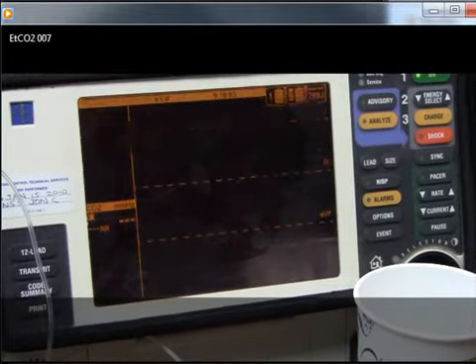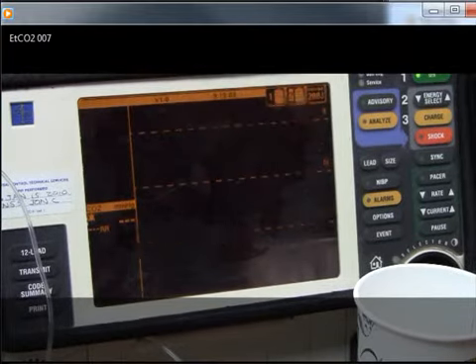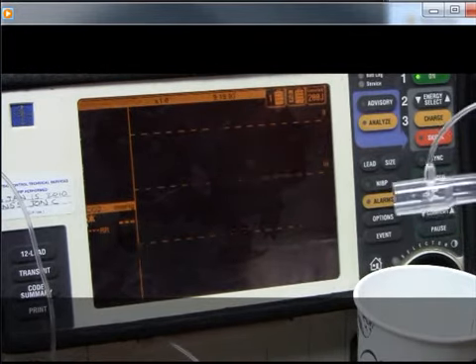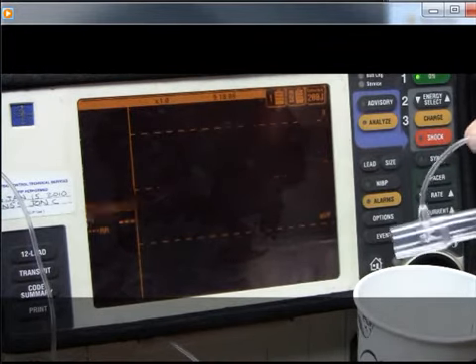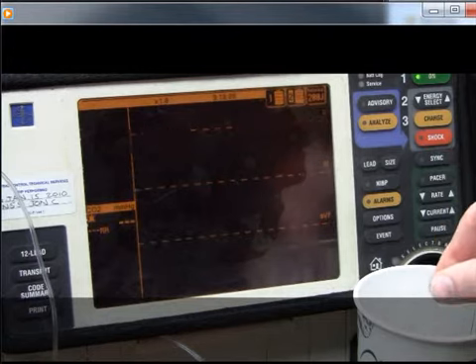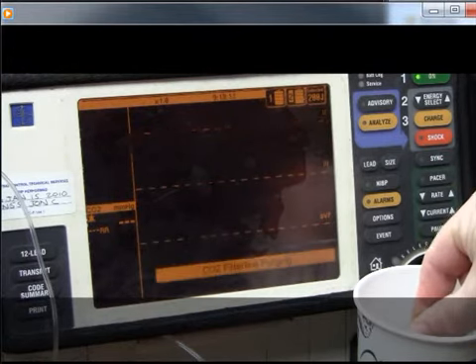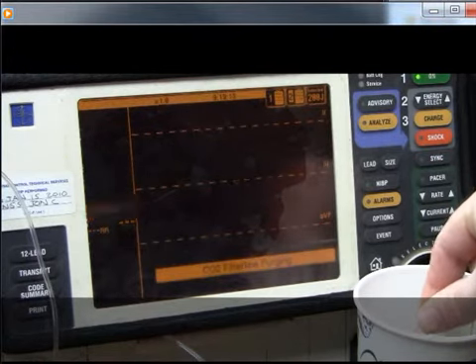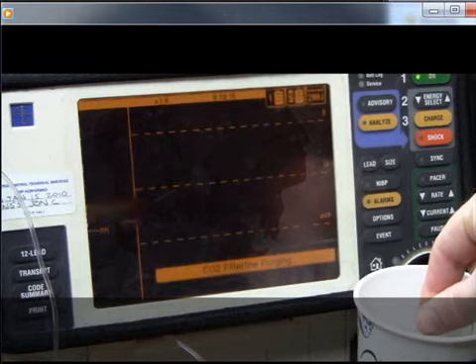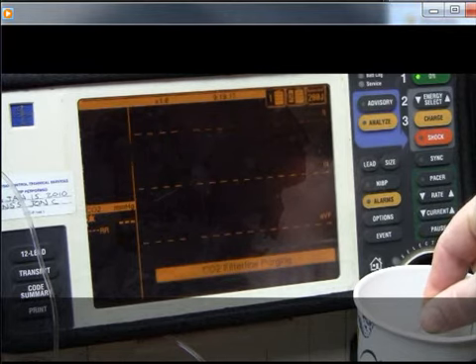There are times when a filter line may be affected by moisture or fluids such as emesis. When this occurs, the monitor will identify the problem, most likely immediately, as either a filter line purge or blockage. When this happens, remove the filter line and replace it. Do not attempt to reuse it.